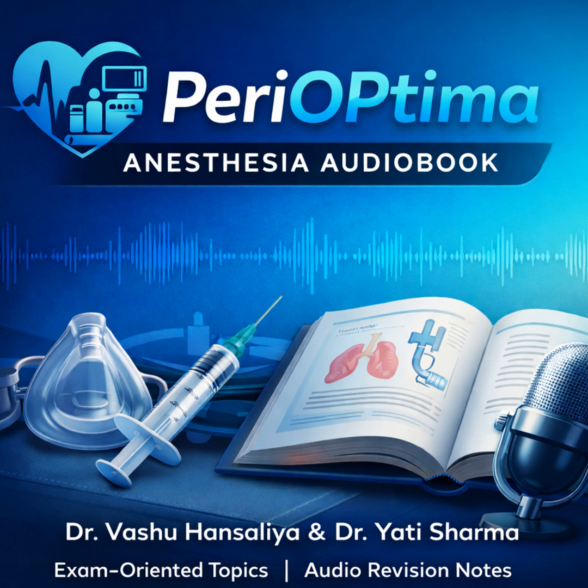Section 12. Scenario. You are in the middle of a case. The oxygen failure alarm goes off. Your pipeline pressure gauges drop to 0. What is your immediate action plan? Immediate action 1. Open the emergency oxygen cylinder on the back of the machine. Immediate action 2. You must disconnect the pipeline hose from the wall outlet.